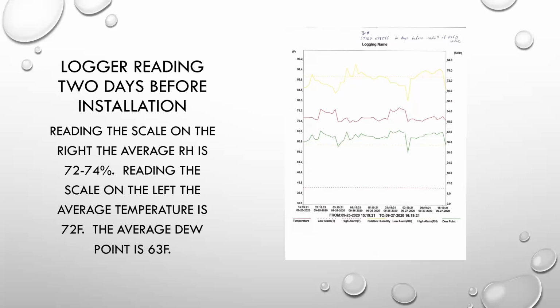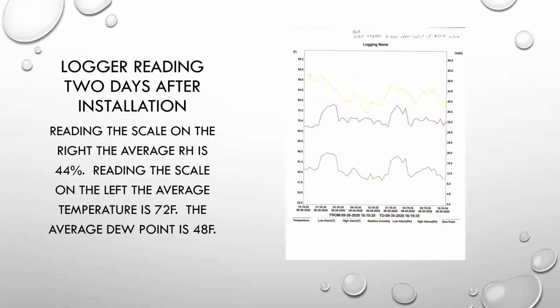That was before they put the RCCD on. When they installed the RCCD, they did the take afterwards. And if you look at the RH scale on the right-hand side, it's way down. It's a lot different now. Now we're looking at an average RH in a space of 44%. Our temperature is pretty much up and down a little bit, but it's averaging out to about 72 where it was at. But also now the dew point's around 48 degrees.